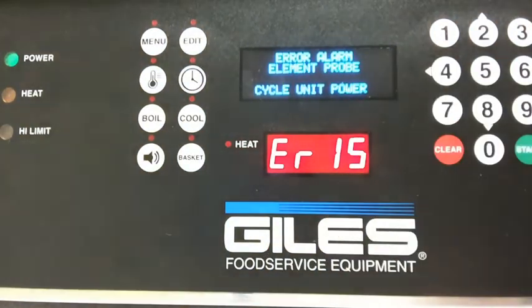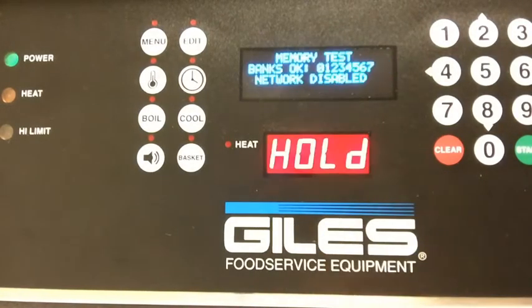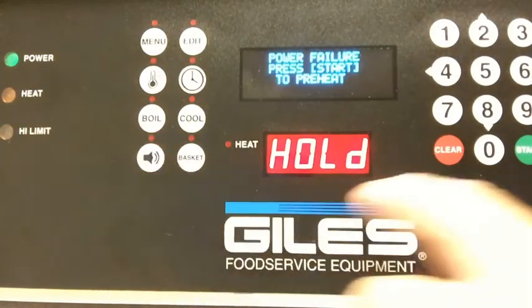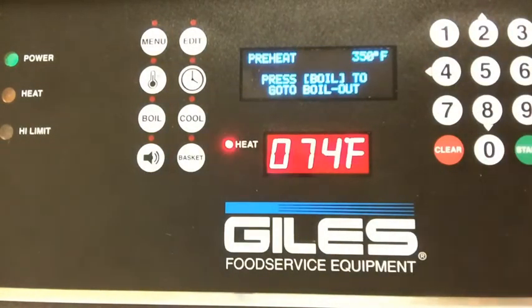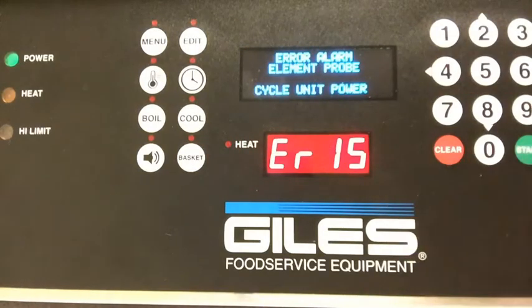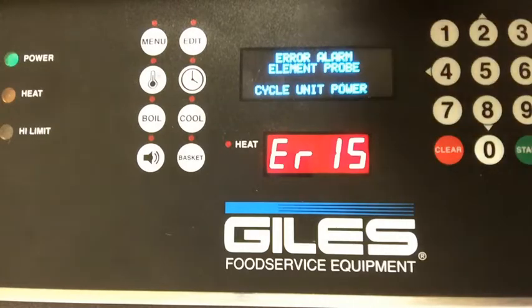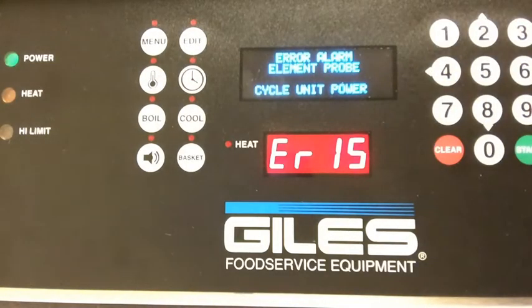Here we are, error alarm, element probe, cycle unit power, error 15. Now, if I go ahead and cycle the power as is suggested, the unit will come back up. Of course, it's going to give me that alarm, power failure. If I press the preheat, it's going to try to heat. Now, if I have not corrected the issue, it's going to come right back. So normally what that means is that I have a broken lead. I have a problem with getting any kind of input. It's not seeing that element sensor. So we need to try to figure out what that problem is.